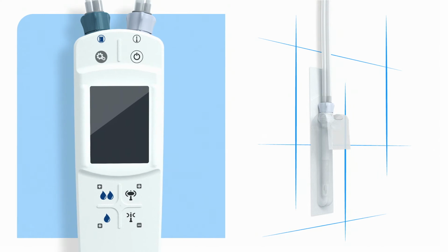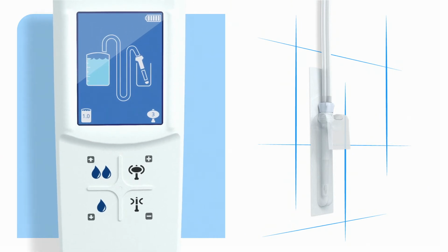Make sure your Navina Smart Control unit is turned on. Once it's on, press the Deflate button to go to the activation mode. Press and hold either one of the water flow buttons to start the water flow. Hold until the water level has reached 3/4 of the length of the catheter. The water activates the hydrophilic surface, which makes the catheter slippery. Now we're ready to start the irrigation.